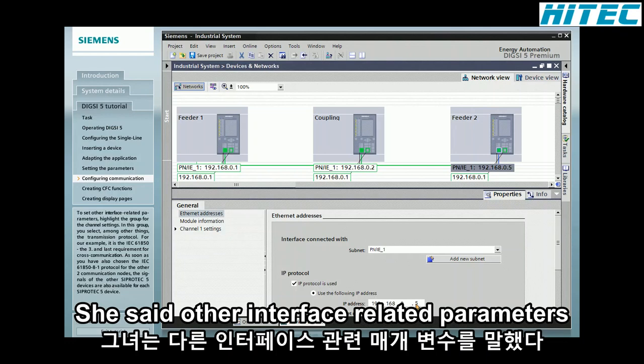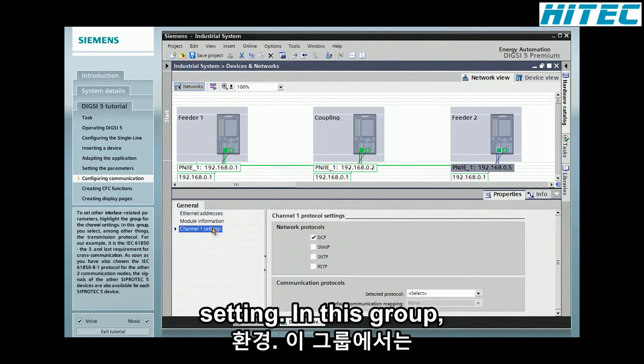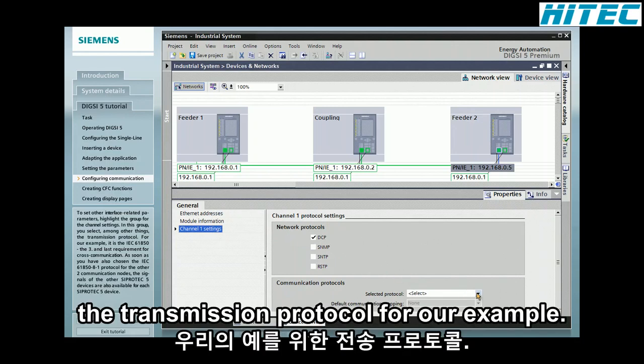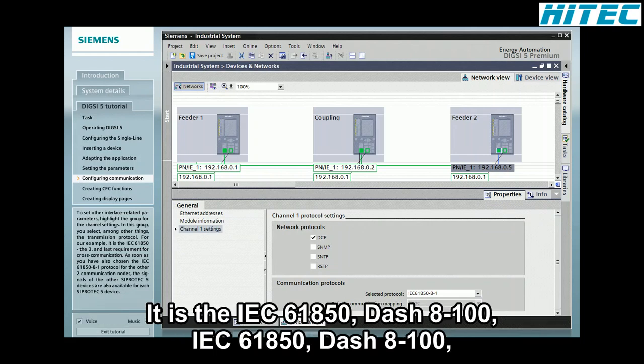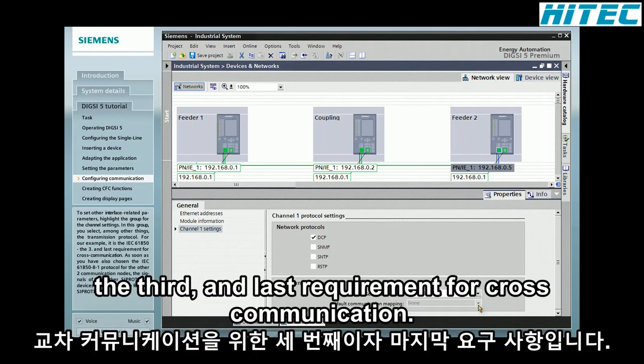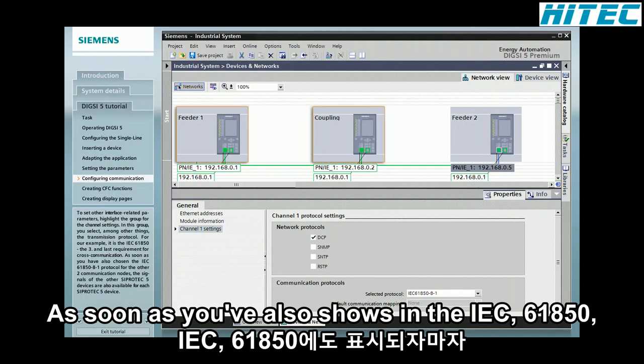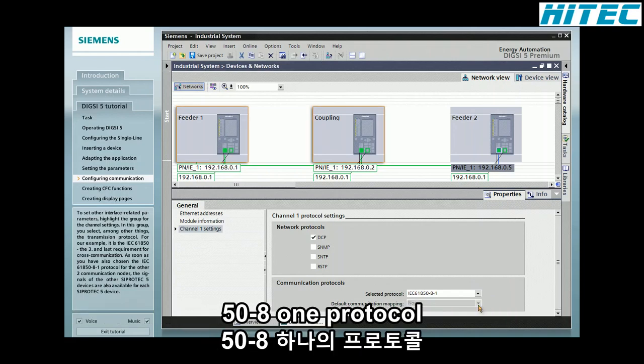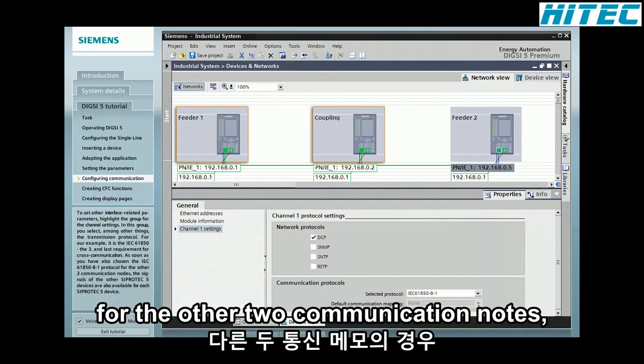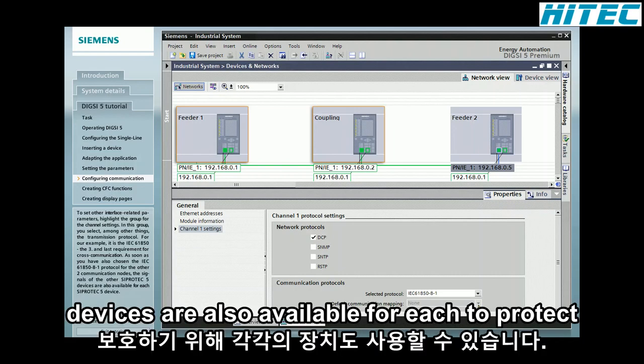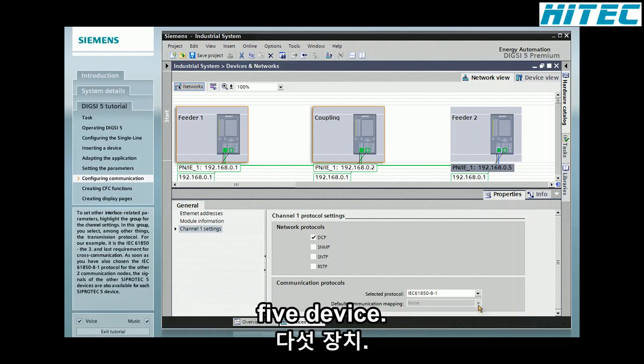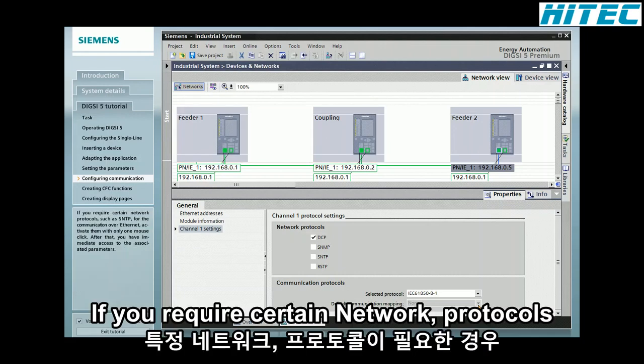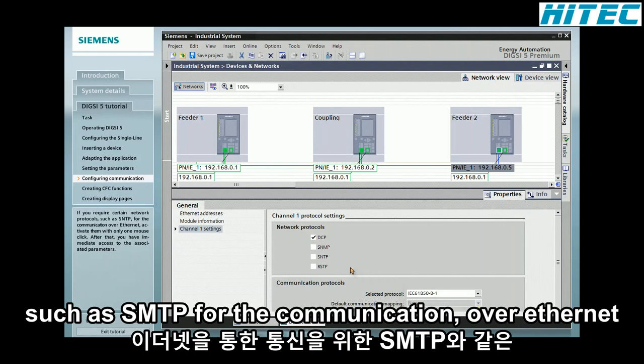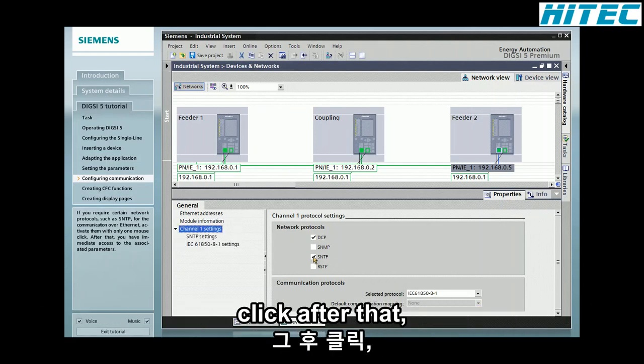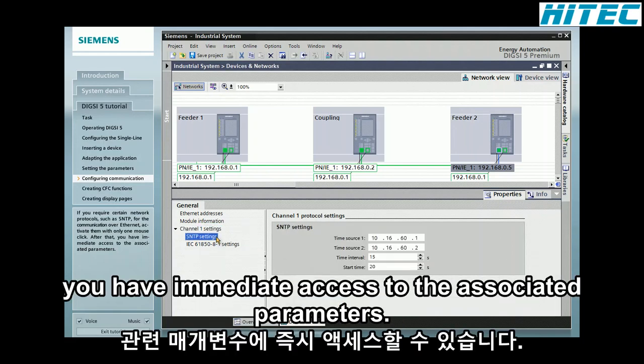To set other interface-related parameters, highlight the group for the channel settings. In this group, you select, among other things, the transmission protocol. For our example, it is the IEC 61850-8-1, the third and last requirement for cross-communication. As soon as you've also chosen the IEC 61850-8-1 protocol for the other two communication nodes, the signals of the other SIPROTEC 5 devices are also available for each SIPROTEC 5 device. If you require certain network protocols, such as SNTP for the communication over Ethernet, activate them with only one mouse click. After that, you have immediate access to the associated parameters.